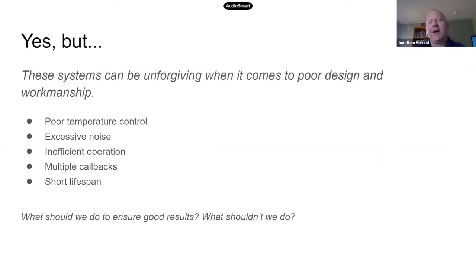So that's the good news. The bad news is that these systems can be really unforgiving when it comes to poor design and workmanship. And if you don't get these right, you'll end up with poor temperature control, excessive noise, inefficient operation, a cycle of callbacks where you aren't able to resolve the underlying problem, and ultimately a short lifespan and a low level of customer satisfaction. And one of the scary things about scaling something up is if you scale up something badly, you're going to end up with a lot of problems. So one of the things I'm really passionate about is getting things right with air source heat pumps. And it's not that hard to do.